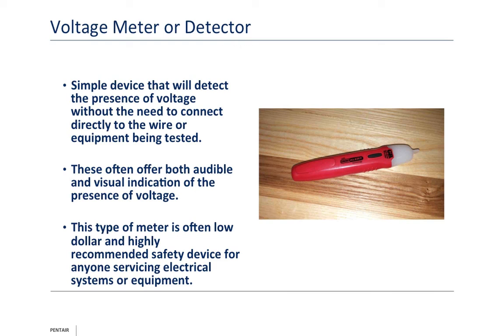That is my first step. If I'm still in doubt, or more importantly, if I do detect voltage, especially on ground, I would then pull out my voltmeter, set it for volts AC, and from ground to any metal, say the junction box, the conduit, maybe the unpainted screws on my main box, I would look to see if I have more than a half a volt. If I do, then I've got to figure out what's wrong with my ground.